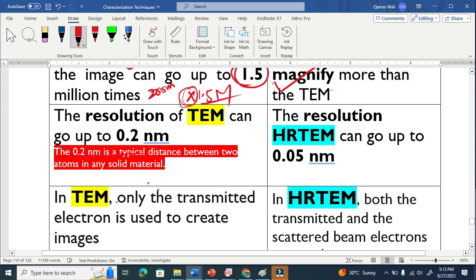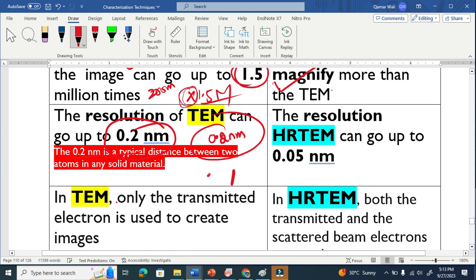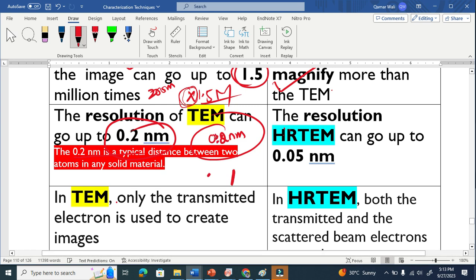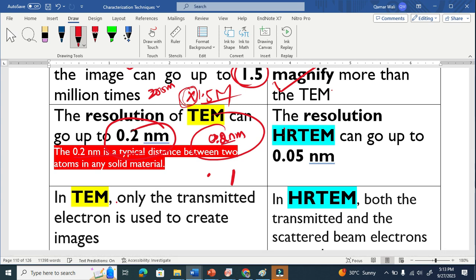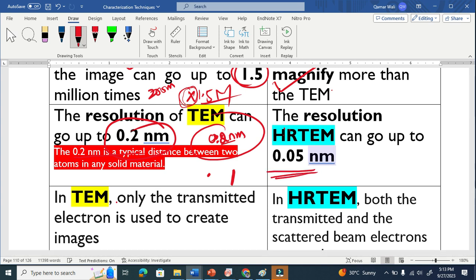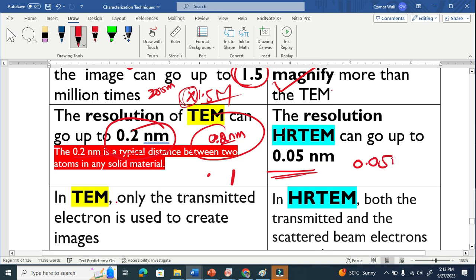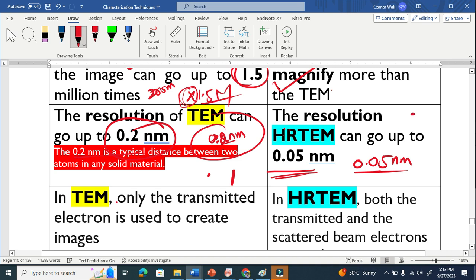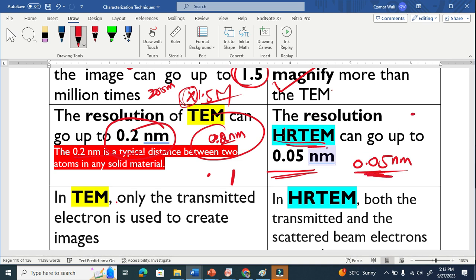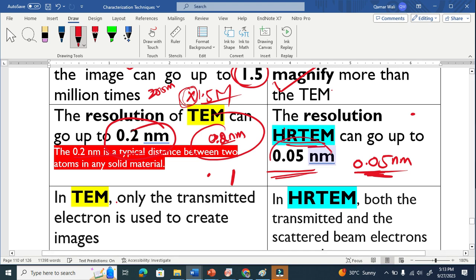The resolution of TEM can go to 0.2 nanometer. This means that you can see a 0.2 nanometer object as separate. If it is a line, if it is a dot or whatever. You can see the 0.2 nanometer object as a separate entity. This is how resolution means basically. In the case of high resolution transmission electron microscopy, you can see very small objects as separate. This means that if you put there a small object of 0.05 nanometer size, you can see it with the help of high resolution transmission electron microscopy. This is how resolution works.